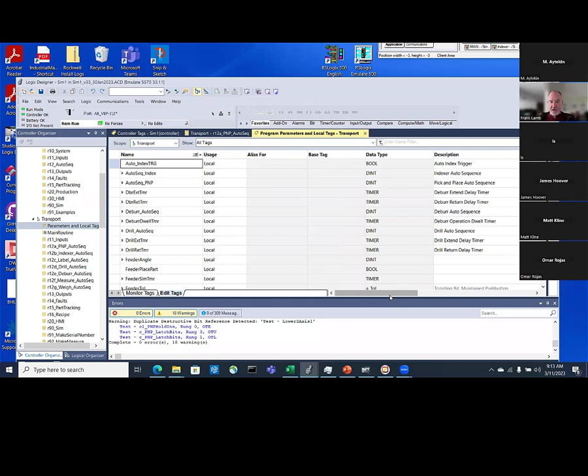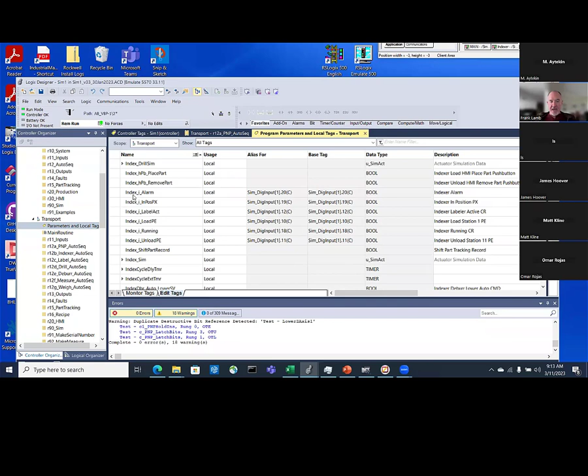Same sequence. I'm at 0. The part shows up. This is the auto sequence trigger, right? Right up here, you can see that the part shows up in the load location. You can also see here, for those of you who are familiar with Allen Bradley, there's something called aliasing. So if I go into my controller tags, I have connected all of my physical inputs in this routine to the simulated inputs right in here. So let's see, if I find edit tags, here we go, and I look at aliases, you can see here that the index alarm, which is an index mechanism, is alias to digital input 0.1.20. If that was alias to a real IO, it would say something like local slot 1 dot 20, right? Digital input.